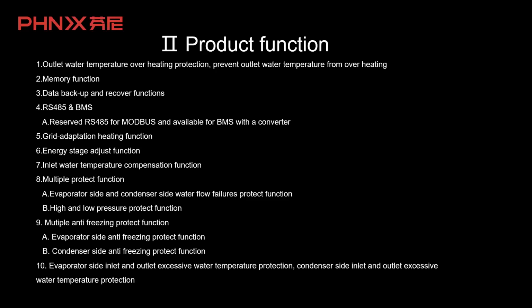I'm sorry for this one. So you mentioned the inlet and outlet excessive water temperature. Yes. So what's the standard delta T, for example, for the evaporator? For the evaporator side, it is 5 degrees. So what do you mean by excessive water temperature? It means more than the heat pump can tolerate. Just for example, the standard is 5 degrees. So if the temperature difference between the inlet water temperature and outlet water temperature is more than 5 degrees, then the unit will go into protection? Yes. Okay.